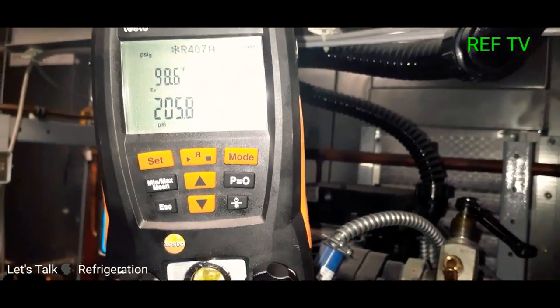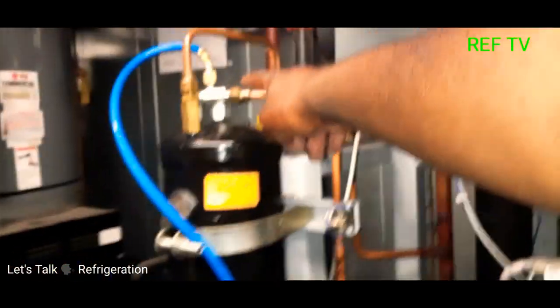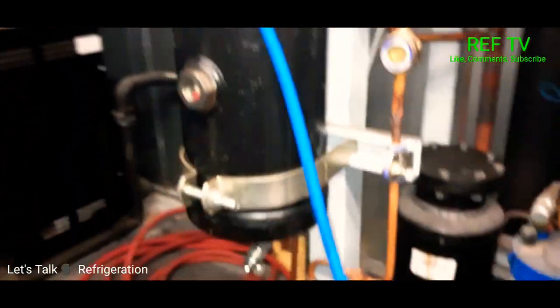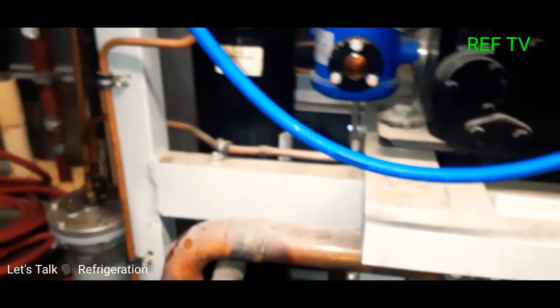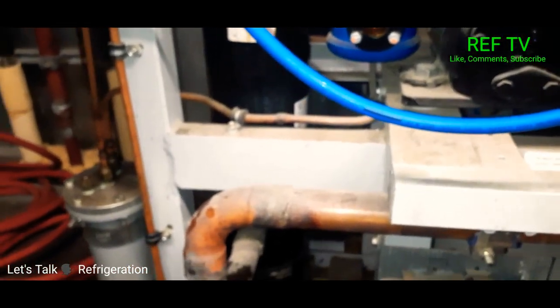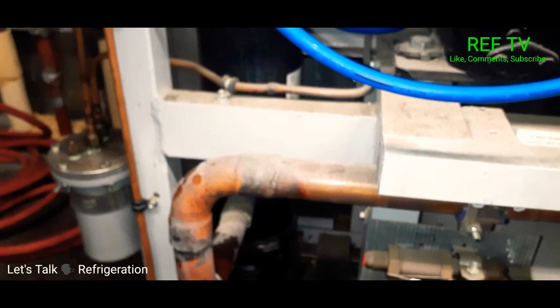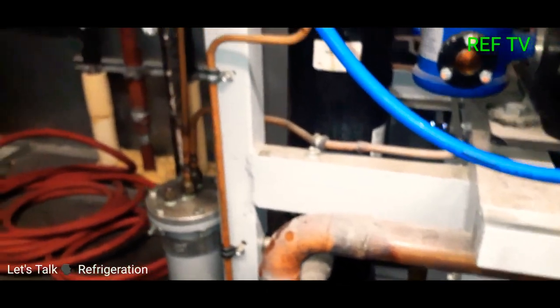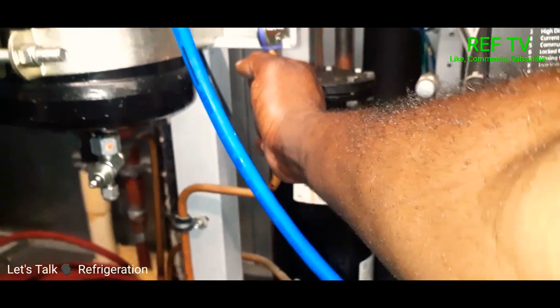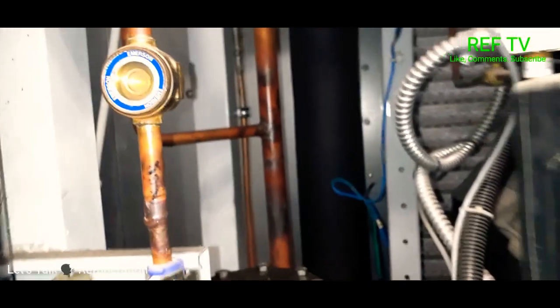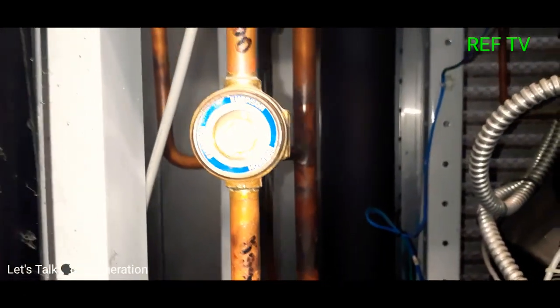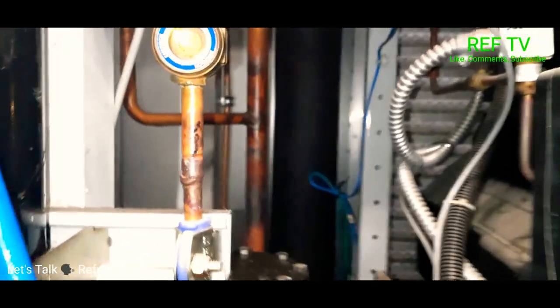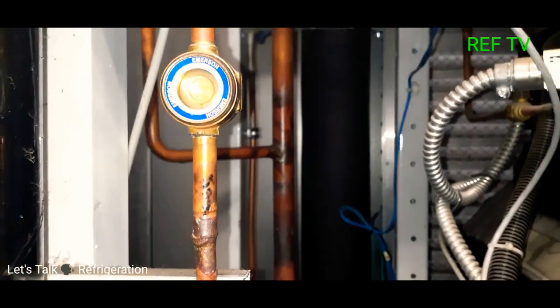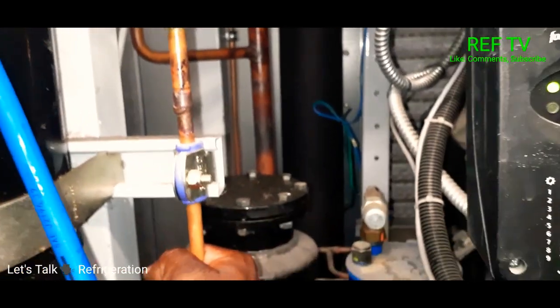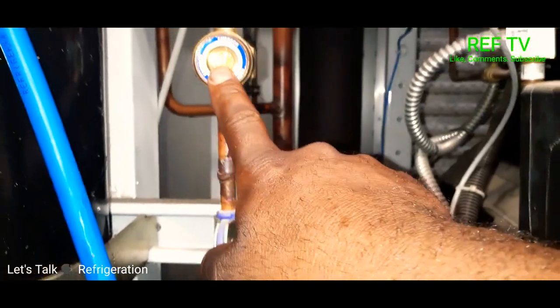You're gonna use that pressure to force its way through here, down through there, and it's gonna go up into that float and move the dirt and debris around, and it's gonna allow oil to feed. When I came here, this line was cool. Also, it had oil in it. If you look at it now, that oil is being pushed back into the oil float, and it's making that rise. Once we open this up, this line is gonna get real hot. Also, you're gonna see bubbles coming through here.